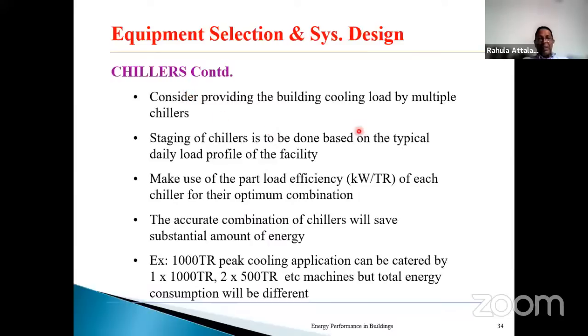Chiller: consider providing the building cooling load by multiple chillers. So we saw that looking at the type of the building. Building load is not a constant. If building load is constant, one chiller could handle it. But if it is not constant, if there's only a peak at a certain time, a very small fraction, then it's always better to have a smaller chiller to handle the smaller load, a medium chiller for the medium load, and a bigger chiller to capture the higher load. So they have to be sequenced in a proper way.